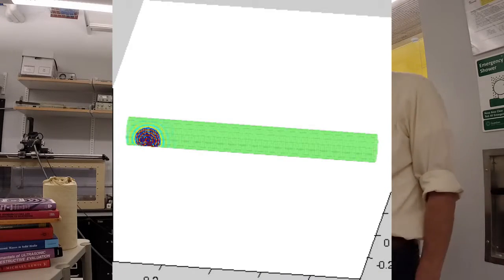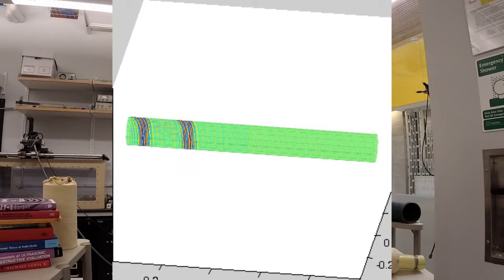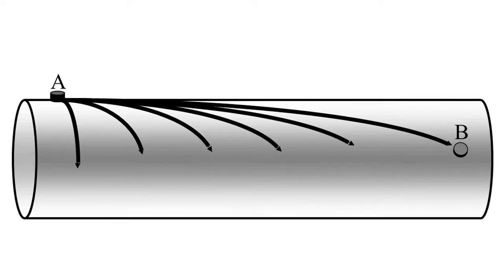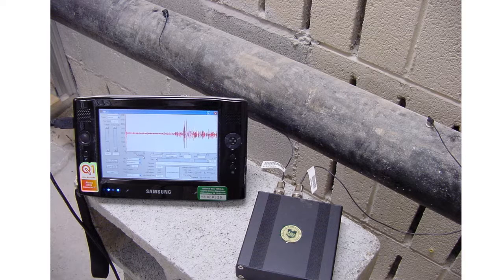So what we do is we broadcast, from a place where you have access to the pipe, mechanical vibrations in the megahertz range - we call this ultrasound. So ultrasound guided waves in the wall of the pipe can travel down the wall, under the lagging, through the bulkhead, and at some other place where you can get access, you can pick up those vibrations on the other side. By analyzing those ultrasonic guided waves, you can tell where along the travel path of the pipe there's a problem, and ideally how serious it is.